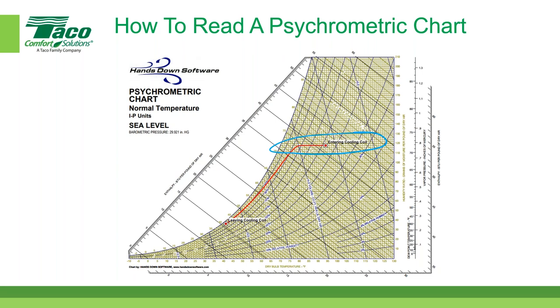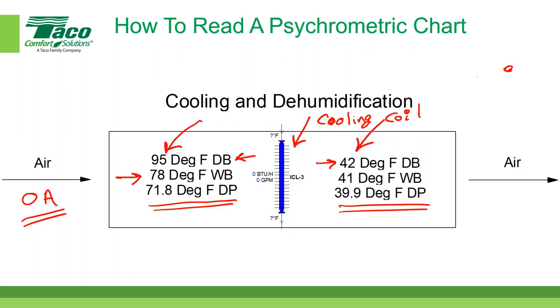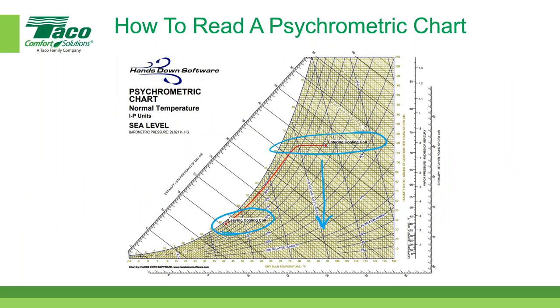And so then it follows this line all the way down until it gets down here where the leaving coil temperature is. So what has happened is that not only has the air been cooled, but because we're dropping vertically in this direction, we're taking moisture out of the air. The dew point temperature was about 72, and now it's down to around 40. So it was over here at about this value, 72, and now it's down at 40, way down here.